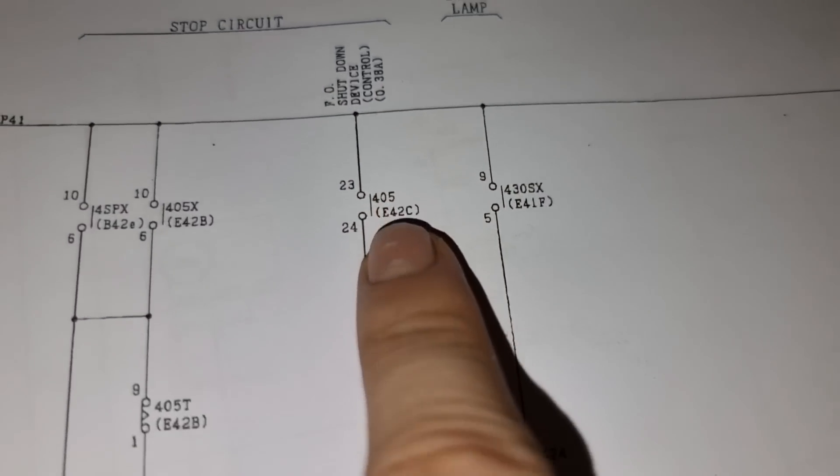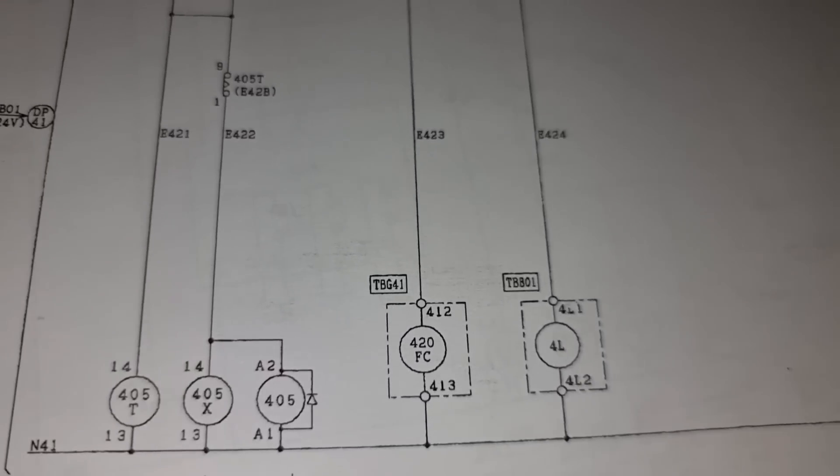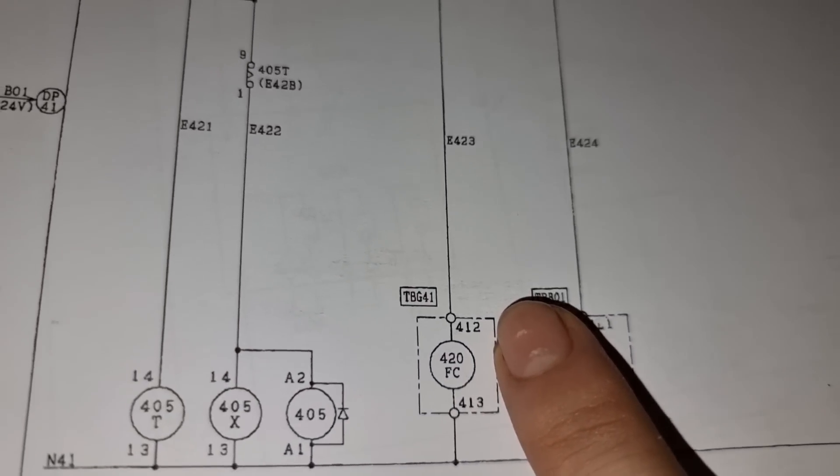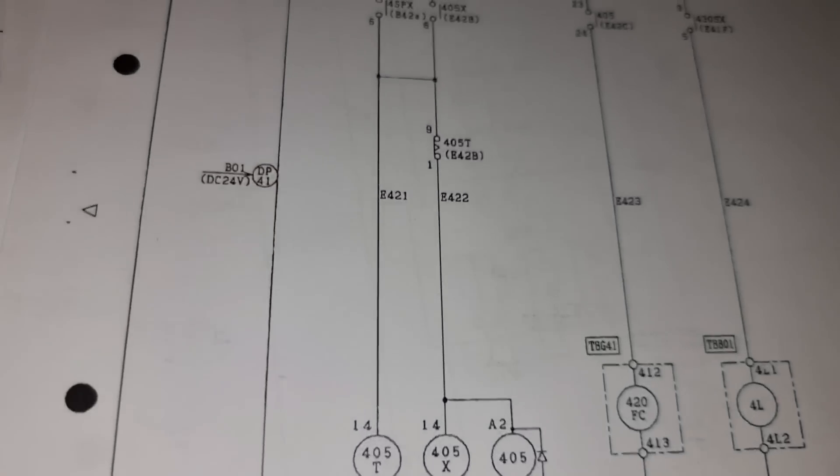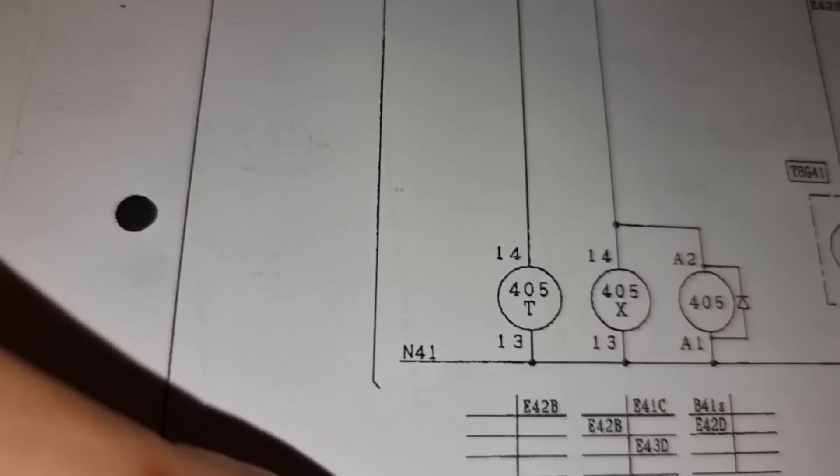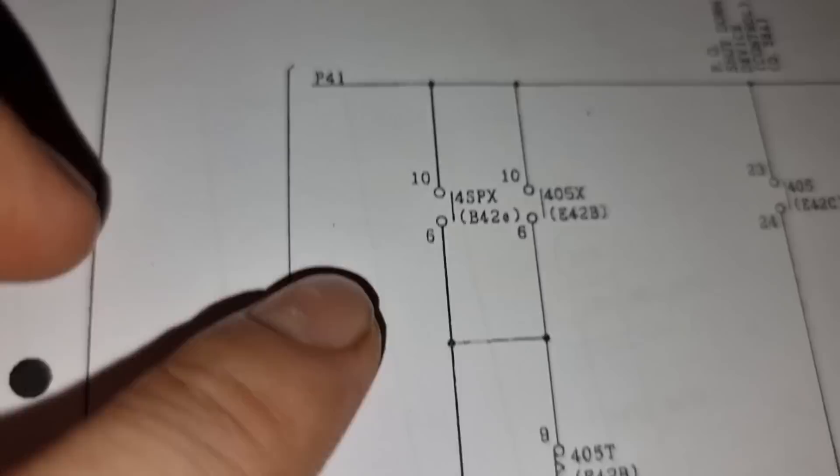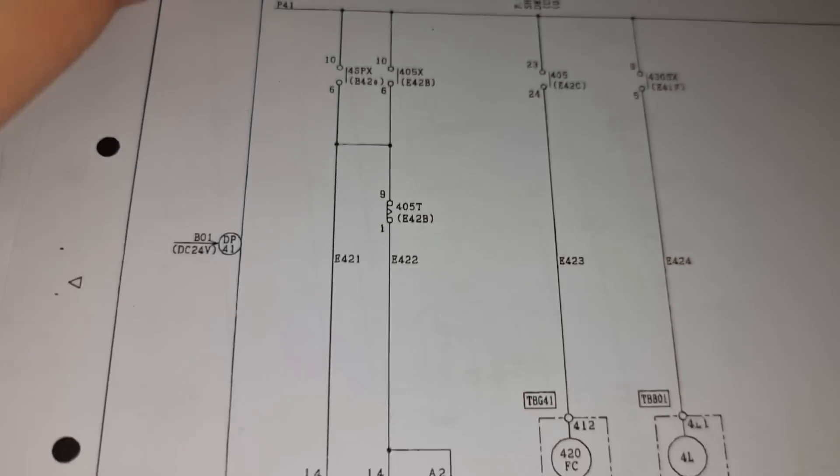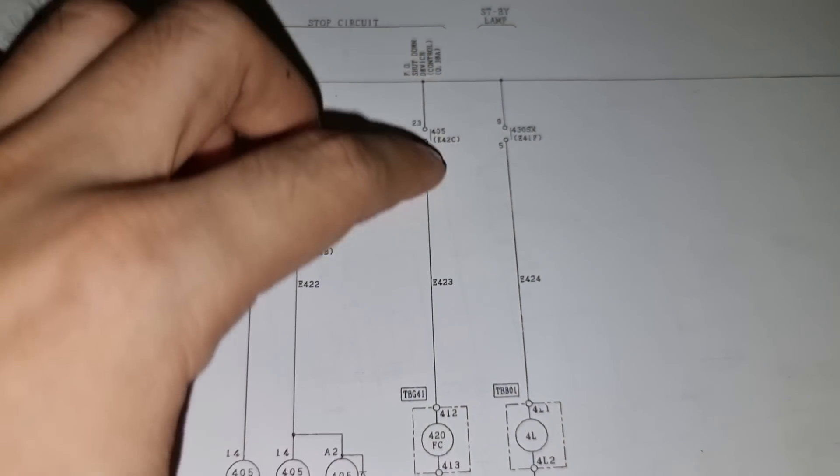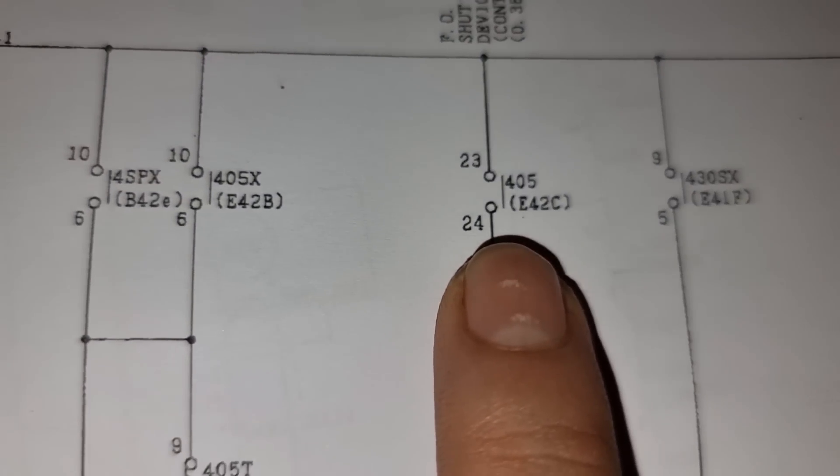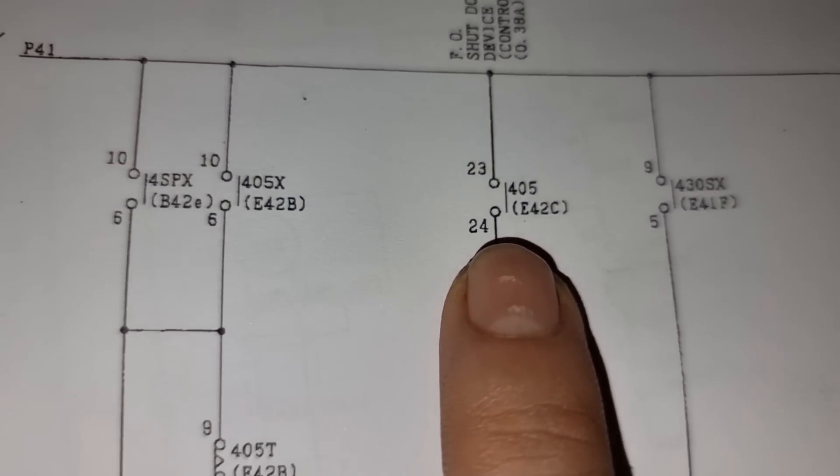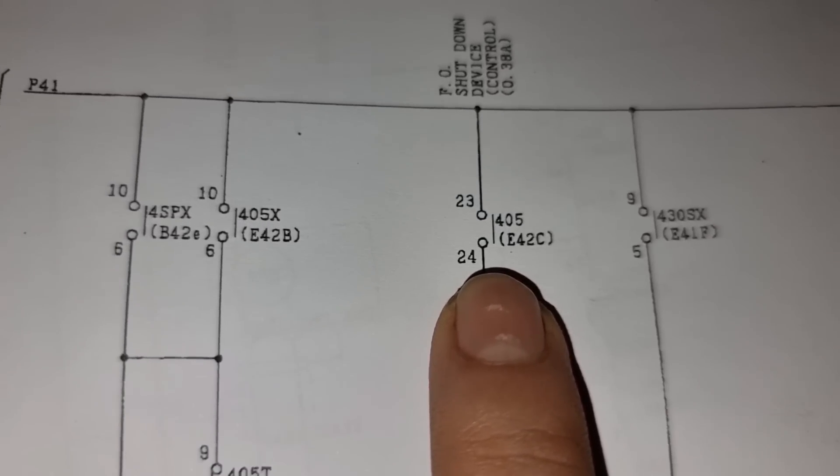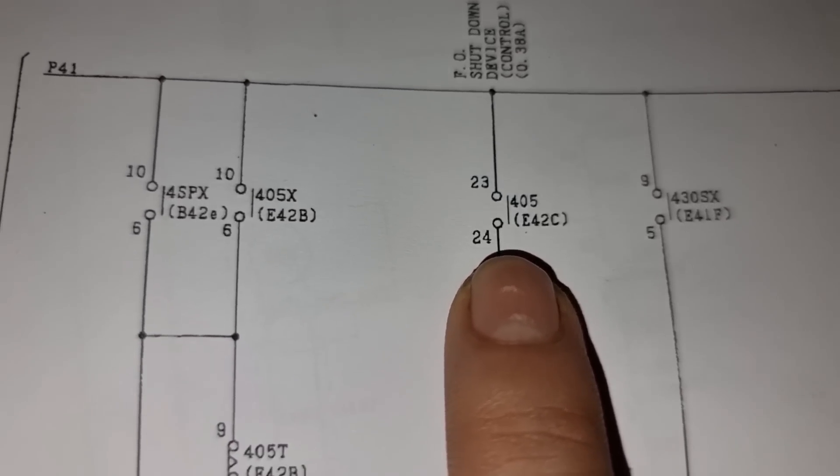This is under the remote operation. So let's measure the voltage on 412, 413. As you can see that these two lines, the F41 or the P41 and N41, they are supplied with 24 volts. And tracing the lines, this 405 should close every time we activate the stop circuit on the PMS system or on our server.